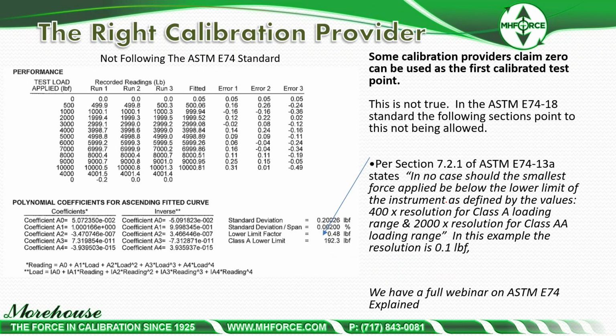Some calibration providers claim 0 can be used as a first calibrated test point. Not true at all. Section 7.2.1 of the standard says in no case should the smallest force applied be below the lower limit of the instrument, as defined by the values 400 times the resolution, and 2000 times the resolution for Class AA. We have a full webinar on ASTM. This is just sloppy. If you have a report like this, you cannot use this device below 500 pounds. People do use it, and they are not in compliance. If you're using a device with 0 as a first point and you're using it between 0 and the next non-zero force point, you're wrong. Stop doing it immediately. It's not right.